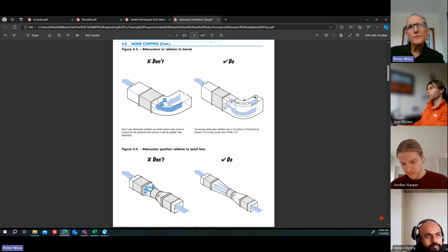And because the splitters are horizontal, that's getting a more even distribution through the attenuator. So that's an important one to be aware of because this can happen a lot. You don't want to put vertical splitters after a bend because you're starving the attenuator of airflow on the inner radius side. Does that make sense?